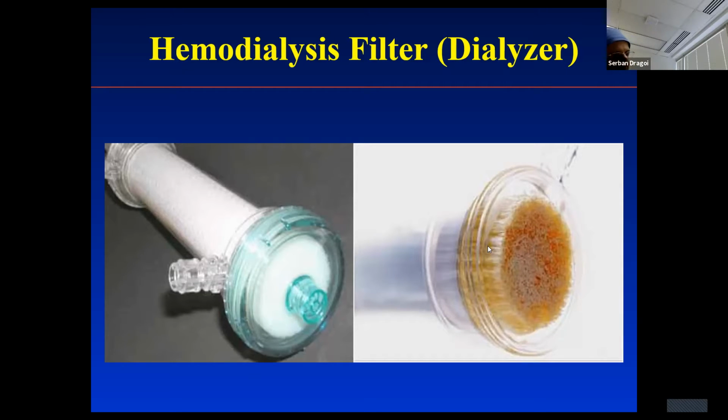think about, say, a vent going through your roof, like the vent that goes into your bathroom, and this has to be sealed, otherwise it will rain inside your house. So it's very tightly sealed here. So the blood from this compartment does not go back into the compartment where the dialysate is. It's actually like a swamp here in between all these straws. They are floating in dialysate, and here they're again very tightly sealed, and they are peeking through this surface and then collecting all the blood through this collecting cap.